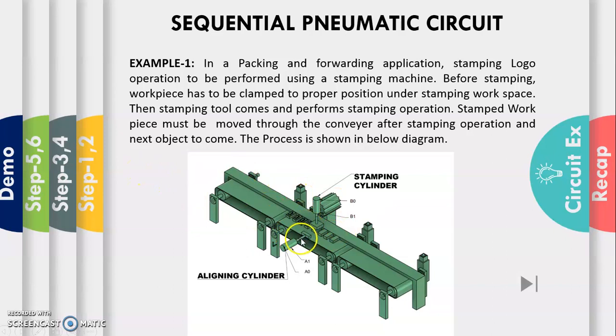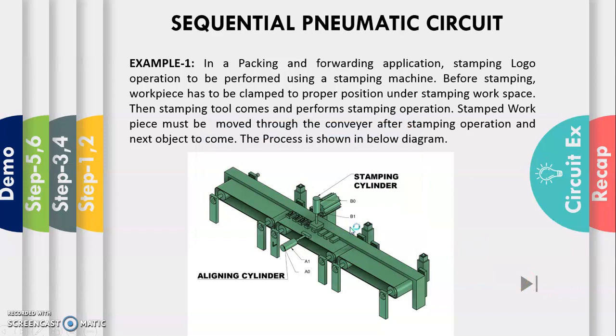For that I am going to clamp the soap bars using cylinder 1, which is connected horizontally, and a vertical cylinder is used to make the stamping operation, such that I can do this two cylinder control using pneumatic actuation, and the pneumatic actuation will be in a sequential form. So I will go with one simple demonstration of my application here.